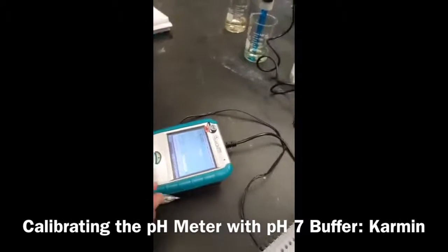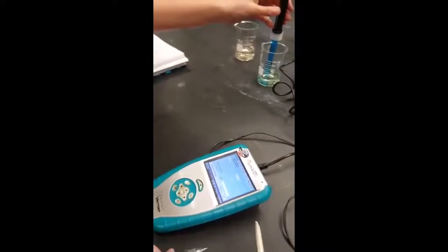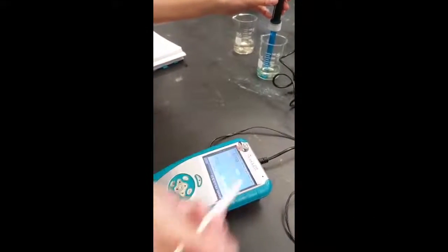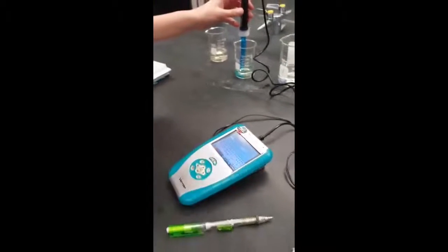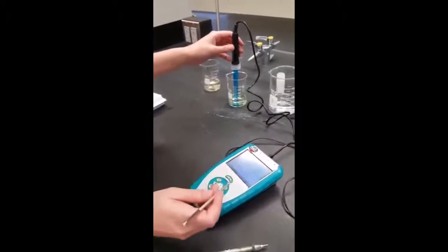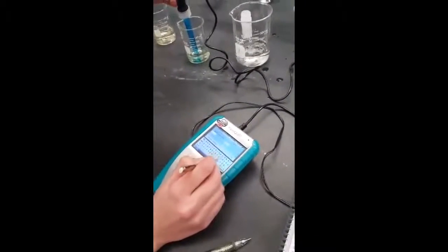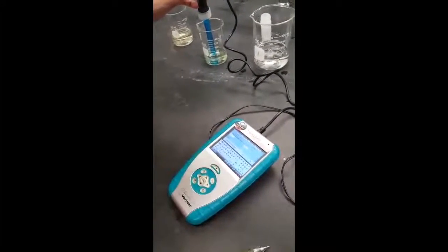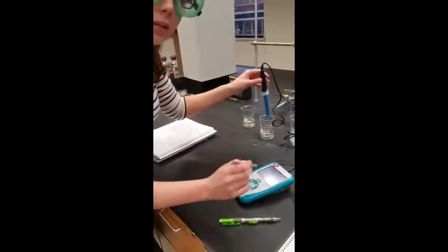I have removed the electrode from the storage solution and rinsed it with distilled water. Now I am calibrating the pH meter by placing the electrode in the pH 7 buffer solution. To set the meter for accurate readings, I will select Sensor, then Calibrate, and Calibrate Now.